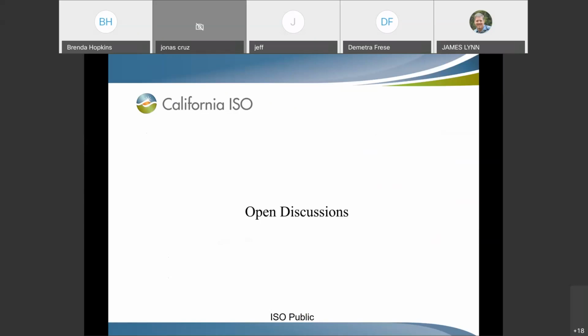Right, and that's actually a very good segue to what I was going to talk about, the base schedule. That's why I wanted you guys to be aware of it. As part of the base schedule initiative that we're going to put in when you guys go live, you can submit a base schedule less than your PMIN. It's referred to as the startup base schedule. And it's to show that a long start unit is starting up the whole time, and those megawatts should be counted for your resource plan.